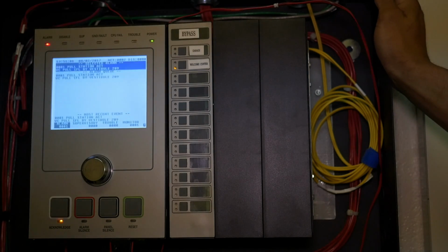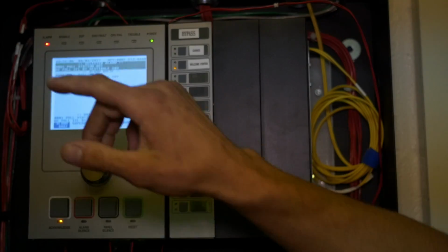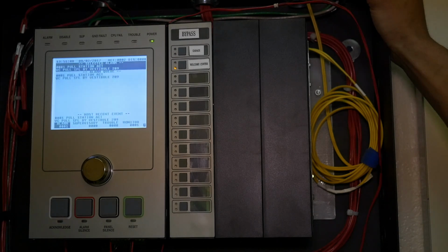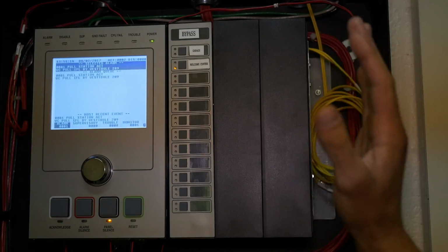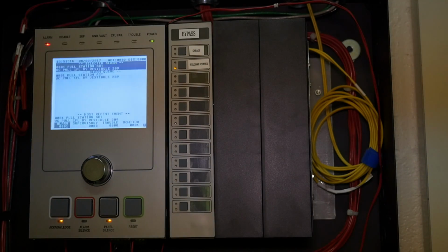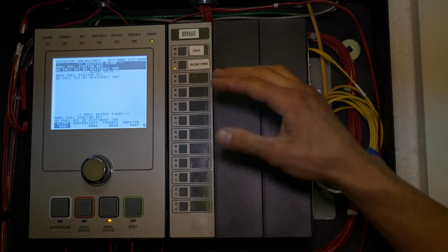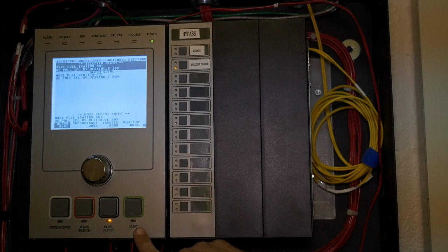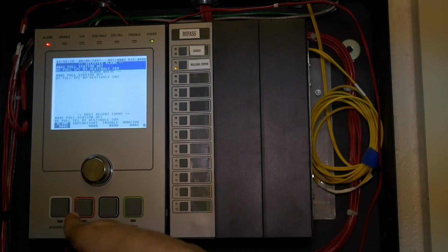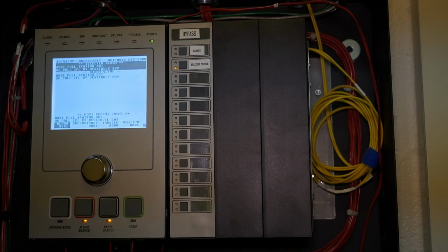So he pulled the Welcome Center pull station, first floor by the vestibule. As you can see, there's an alarm. But the first thing you want to do, probably to make it less annoying, is hit panel silence, and that's going to silence the panel. Now, the horn strobes aren't going off right now because we have the disable on, but if this was not active and the horn strobes were going off, this panel silence is not going to silence the alarms. It's just going to silence the panel from beeping. You would have to come over and hit alarm silence, and that would actually shut the horn strobes down and silence everything. And then you can go and investigate after you've looked at what it is.